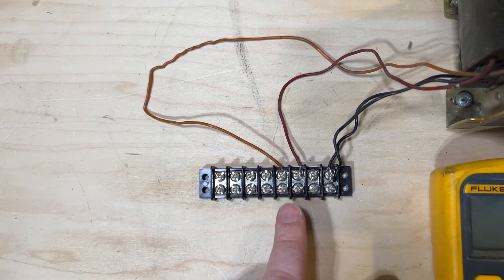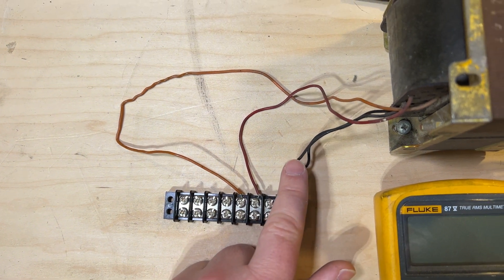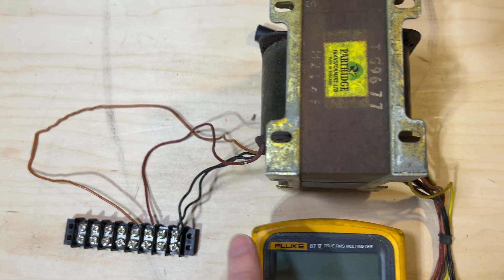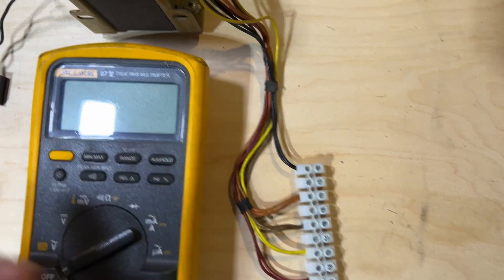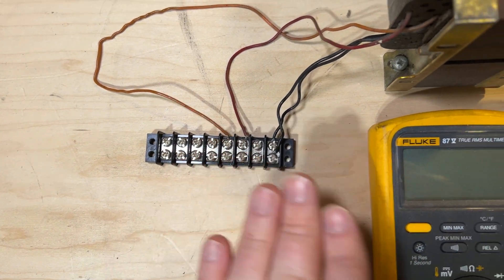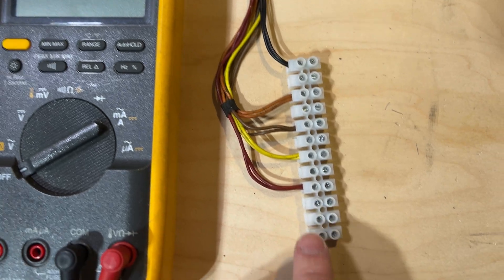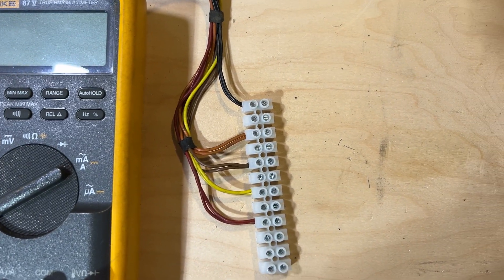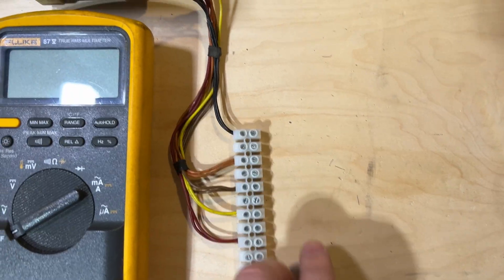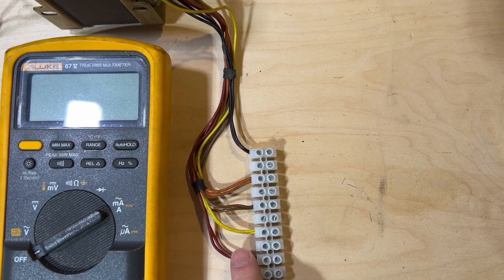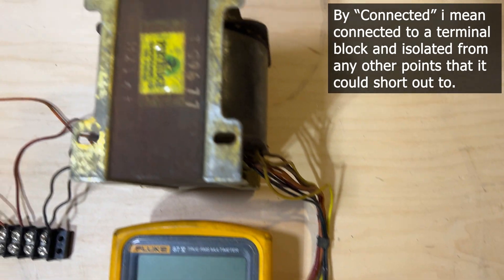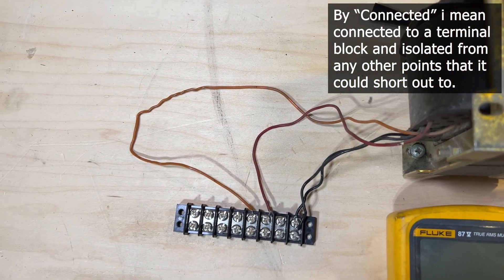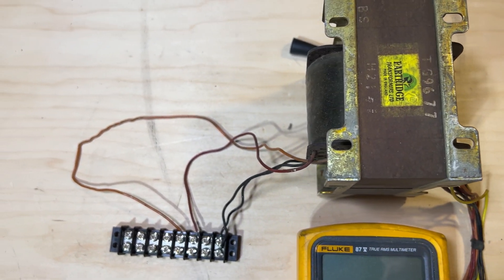So, the important thing here is that we isolate all of the wires, except for those that we assume or know to be safe to connect together. Isolate each. We're going to be very careful when there's voltage on this to not brush our knuckles against anything. Even these terminals that are inside here, if you accidentally touch, you'd get zapped. So, you want to be very conscious of that. And then we want to make sure that all wires are connected and isolated, even if we're not going to be testing them. We want them to be connected and not just be a flying lead if it's in a position where it could accidentally short something out and hurt our transformer, or more importantly, hurt ourselves.